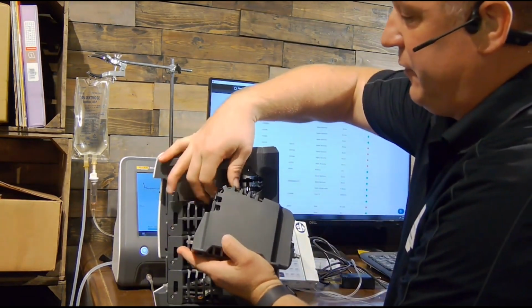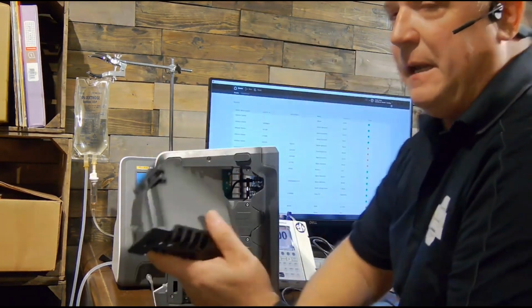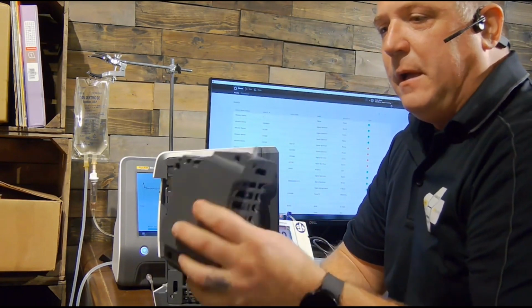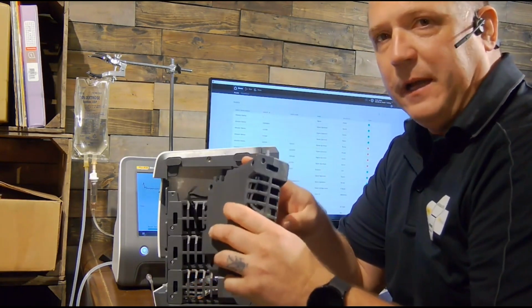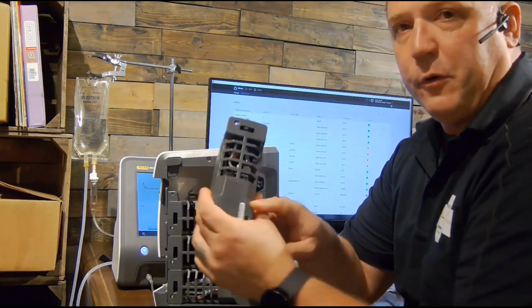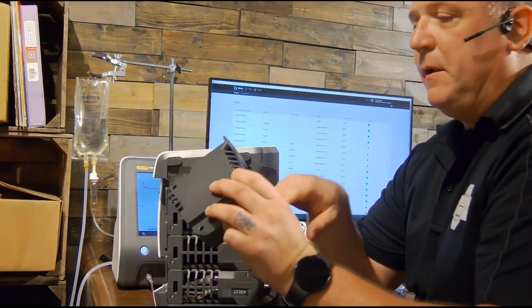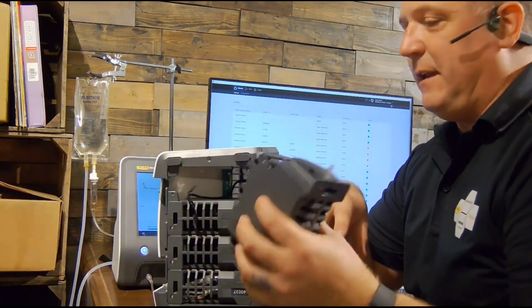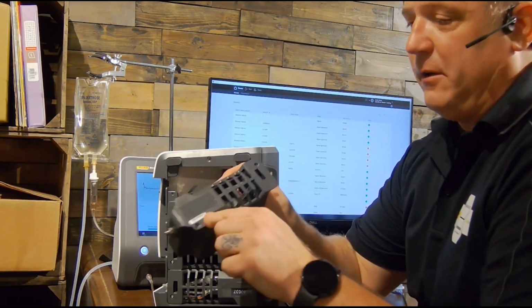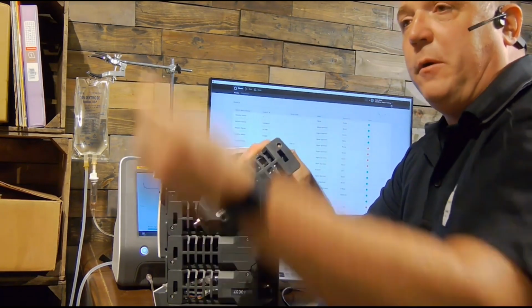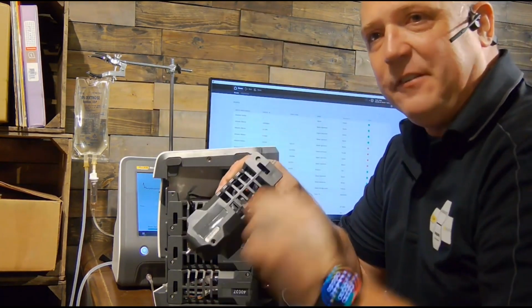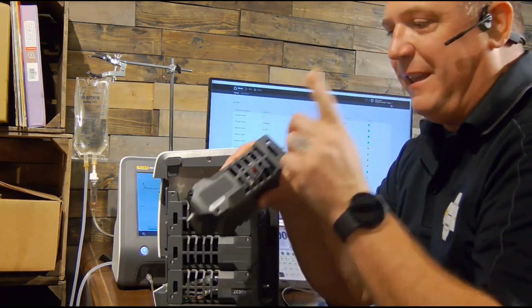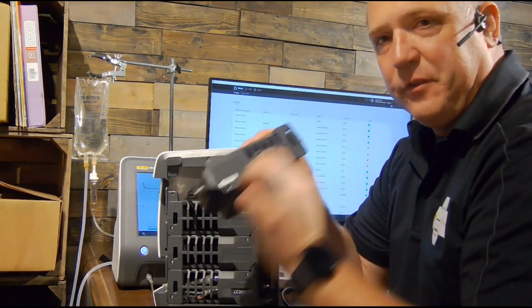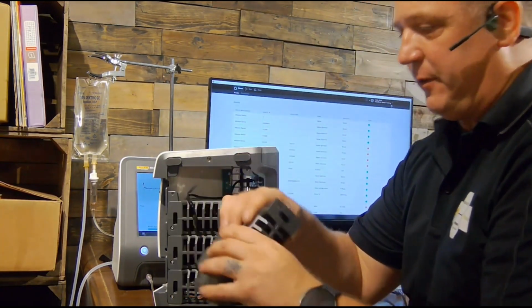I'm going to disconnect it. And this is what I sent in for calibration. The calibration is housed right on a device along with the serial number. So it corresponds to the serial number in this pump. So if I get this back and I set it into a different IV pump, it's not a big deal, because this serial number will be recorded into the IDA-6 and attached to that work order in OneQA. So you know the exact channel serial number that you used for doing your tests.